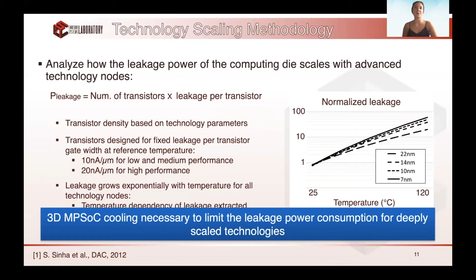Talking about 3D MPSoC cooling strategies, we will compare the efficiency of FCA on-chip cooling with two state-of-the-art methods. The first is the traditional and widely used fan-based cooling. As an example, the fan-cooled Power8 processor reaches a peak temperature of 90 degrees at full usage. The same fan-based solution is scaled to achieve the same peak temperature by increasing fan speed, size, and other parameters.